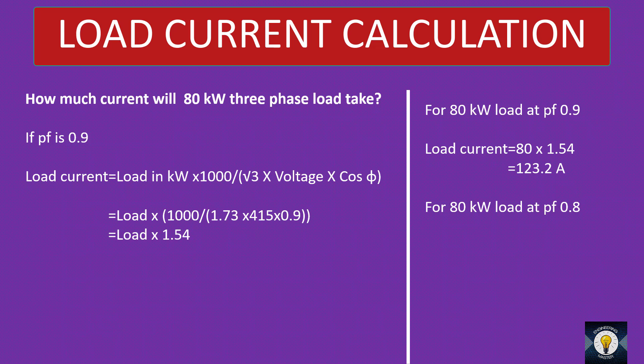For an 80 kW load at power factor 0.9, the load current is 80 into 1.54 — that is 123.2 ampere. For 80 kW at power factor 0.8, the multiplier is 1.74, so 80 into 1.74 gives 139.2 ampere. You don't need a scientific calculator at all to derive the current rating — just remember the multiplier and multiply the load by this value.